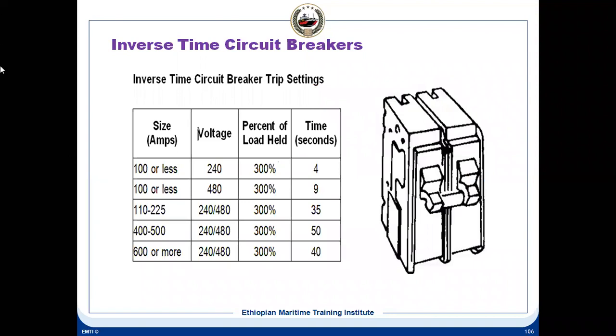You can see here how you size the inverse time breakers. If it is 480 volt, then the percentage of load held is 300%. Time is 9 seconds. So this is a chart. This is from your handout of these charts.